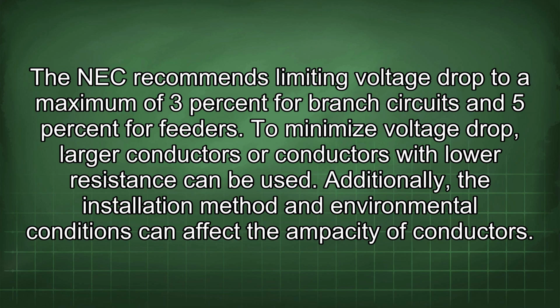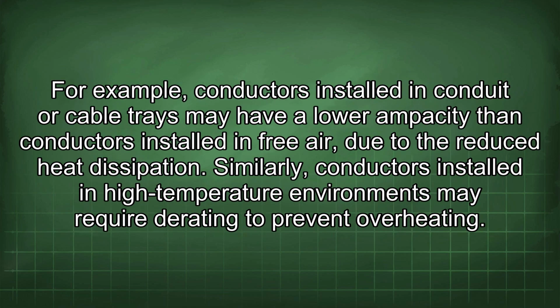Additionally, the installation method and environmental conditions can affect the ampacity of conductors. For example, conductors installed in conduit or cable trays may have a lower ampacity than conductors installed in free air due to the reduced heat dissipation. Similarly, conductors installed in high-temperature environments may require derating to prevent overheating.